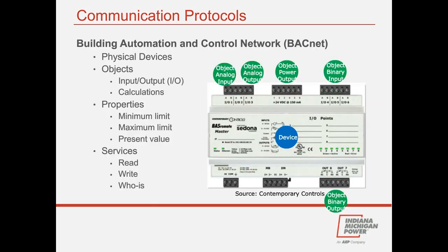What I find more interesting is what's under the hood of some of these field controllers, supervisory controllers. There are 4 basic metrics associated with these: physical devices, objects, properties, or services. A physical device typically has a box like this, which has universal input and output points. This one has 6 universal input and output points and 2 relay outputs. These 6 universal in/outs can be individually configured to either be an analog input, an analog output, or even a digital input.